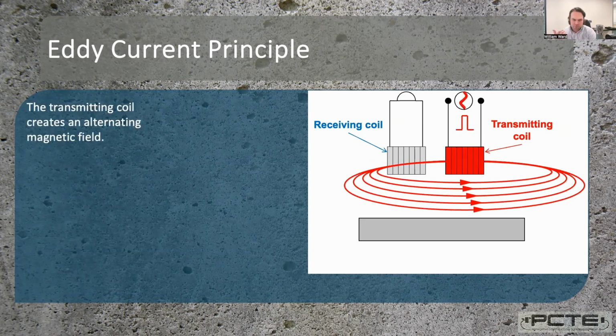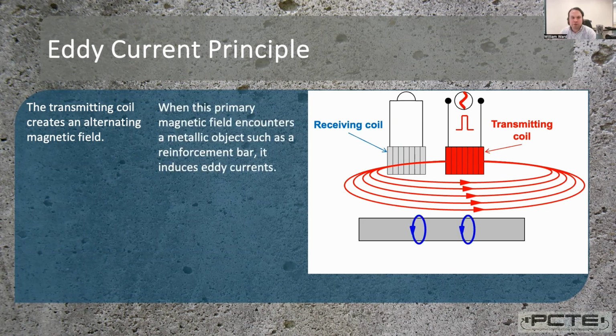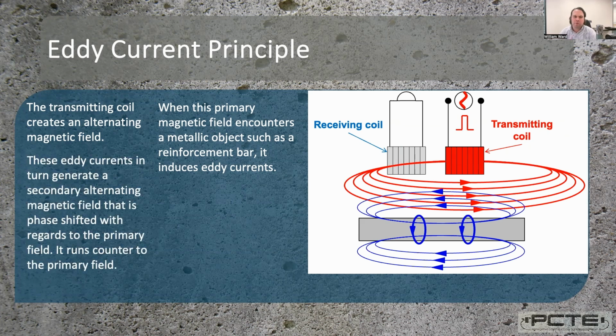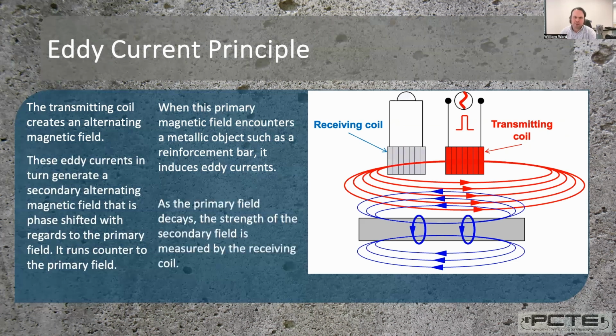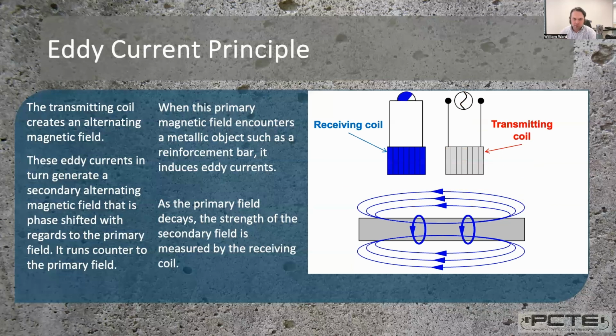The transmitting coil receives an alternating current signal, which introduces an electromagnetic field, and that's transmitted in all directions around the cover meter. And if we bring a piece of reinforcing steel or any other piece of metal within range, it will induce from that electromagnetic field a matching alternating current flow of electricity, which produces its own electromagnetic field around the bar. By turning off our transmitting coil and using a secondary receiving coil to measure the signal intensity of the induced electromagnetic field, we take our measurement.